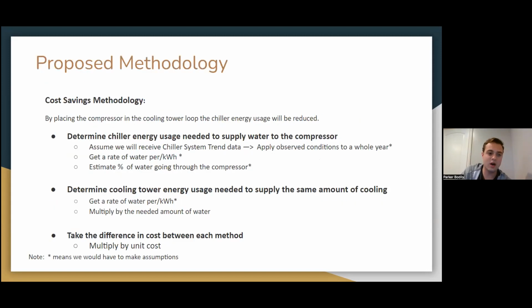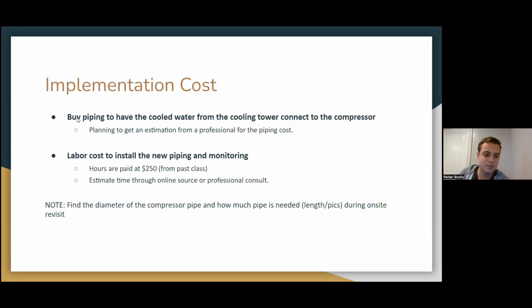And then once you get all that, you can do the implementation cost, which is kind of easy. All it is is buying piping, so you can add the extra pipe and connect the cooling tower water system into the second compressor. That's about all you have to do. You just have to buy the piping and then somebody has to install it. So this is what we think the implementation cost would be. You can check to make sure the water isn't running too hot for the compressors and that everything's running smoothly. So that is our implementation cost.